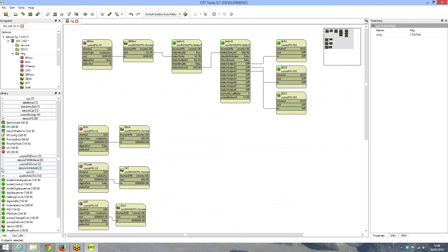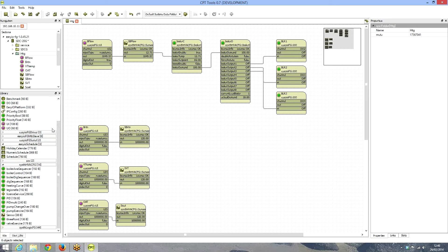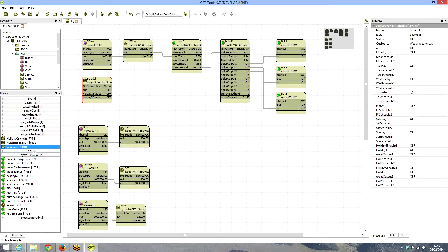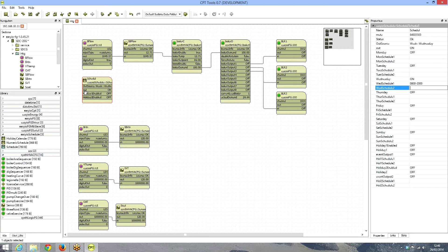We may want the boilers to be time-controlled — running only at certain times of the day. So we go to the schedule kit loaded in the controller, and drag and drop the time schedule. It's currently Wednesday, set from 8 to 20 hours, so the time schedule is on. We connect that to the boiler enable input.